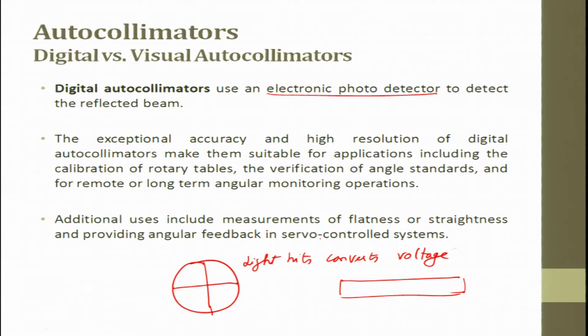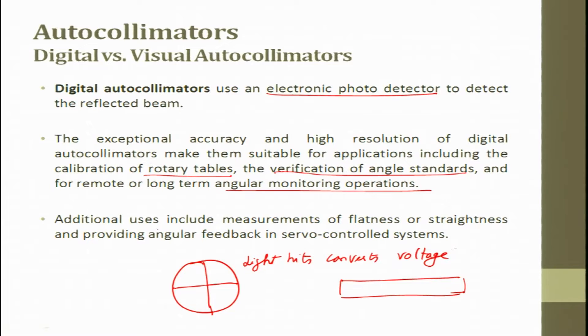The exceptional accuracy and high resolution of the digital autocollimator makes it suitable for applications including calibration of rotary tables used in CNC machines, CMM machines, and other high-precision measurement devices. Additional uses include verification of angular standards, remote or long-term angular monitoring operations, measurement of flatness and straightness (3D flatness, 2D straightness), and providing angular feedback in a servo control system.